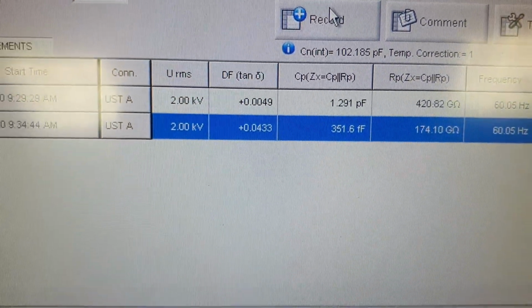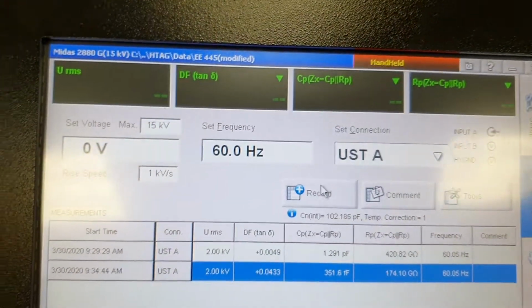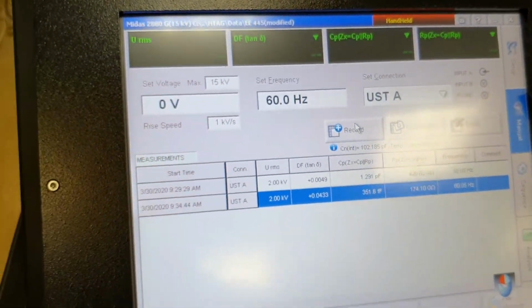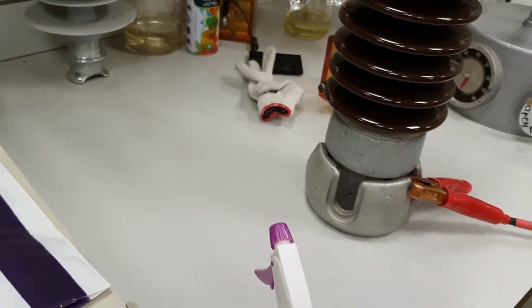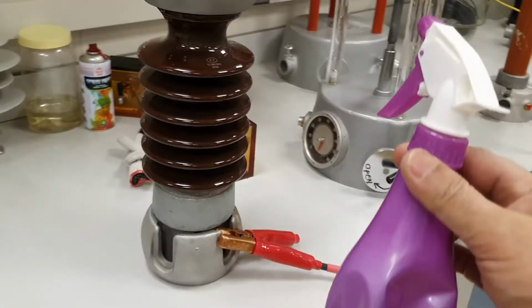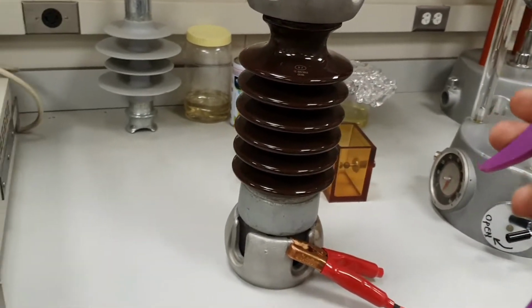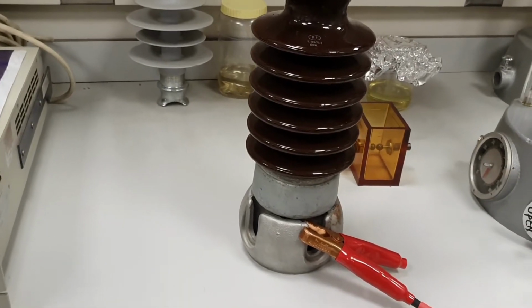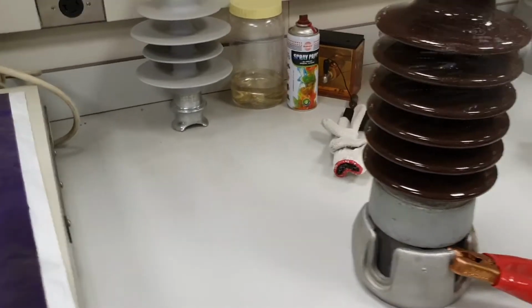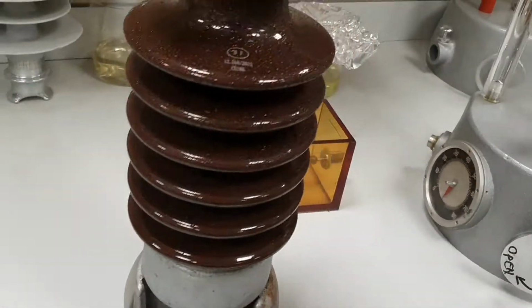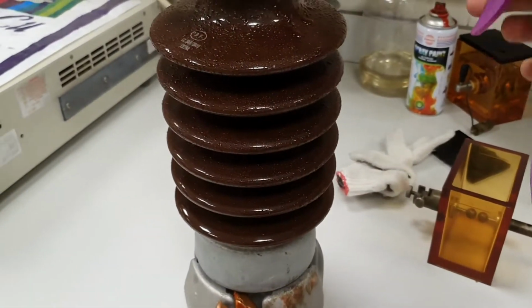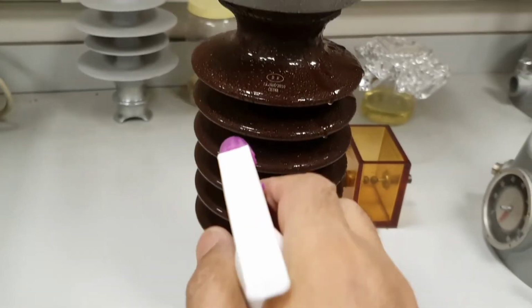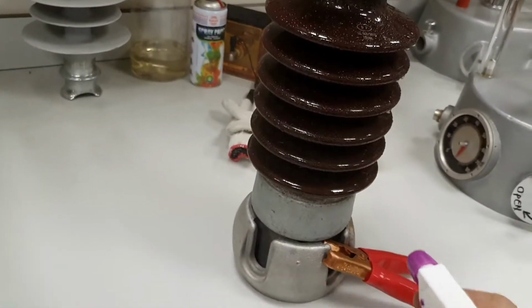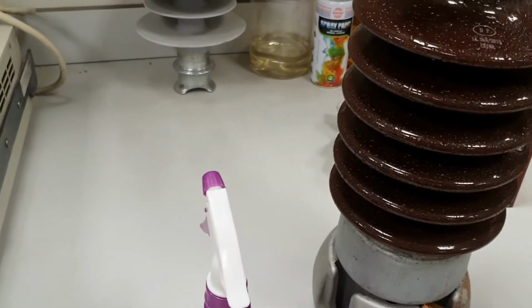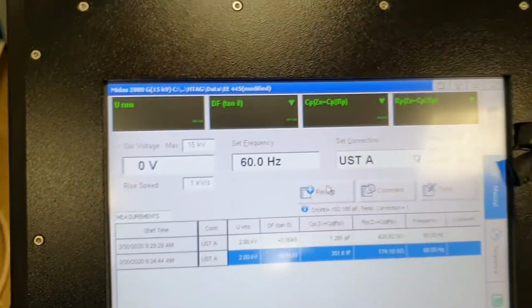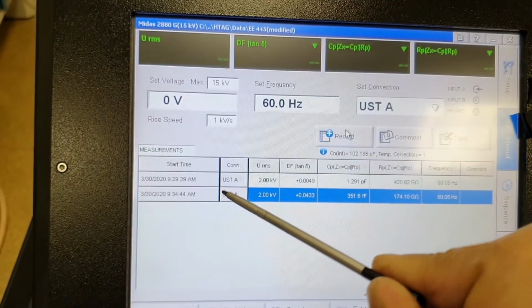So what we'll do now is make the insulator defective. How do we make the insulator defective? We'll use this water here to spray, to make the insulator a bit defective so that there are leakage currents from the top. So we'll make it wet and you'll see there is an increase in tan delta values. So let us start the measurement again after we make this insulator wet.